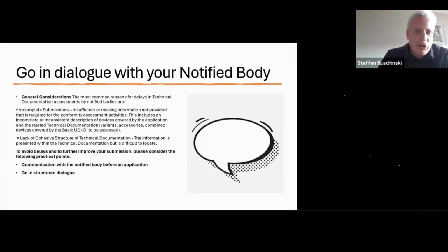I can only recommend going into communication with a notified body before you start an application. You should contact the notified body to clarify the language requirements for technical documentation submission of the individual notified body. This is mentioned in MDR Article 52.12, I think. Manufacturers should contact the notified body to clarify requirements related to documentation, labeling, and methods for submission to the notified body. Additional guidance on topics suitable for discussion with the notified body prior to the submission is also provided in MDCG 2019-6. This must be section 163. This is the so-called structured dialogue.